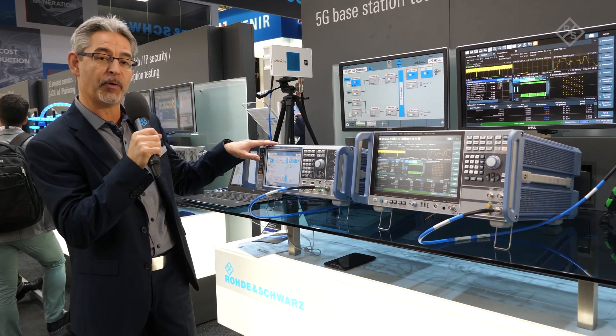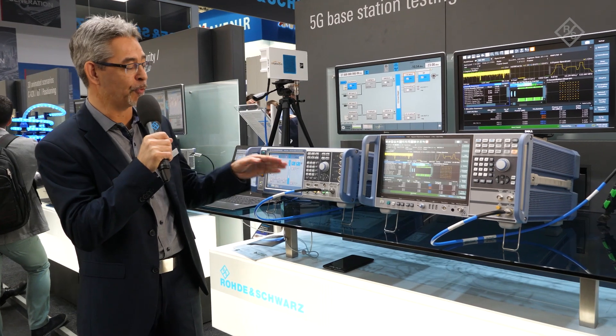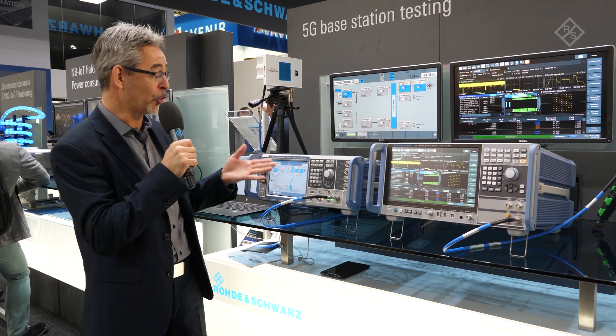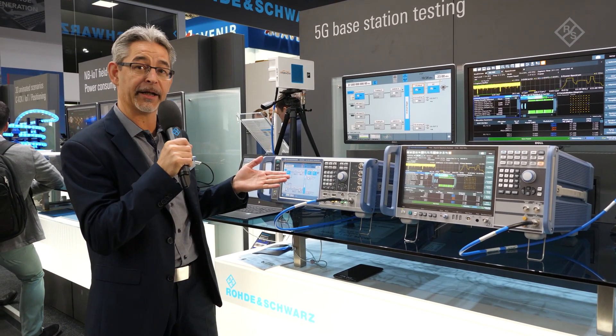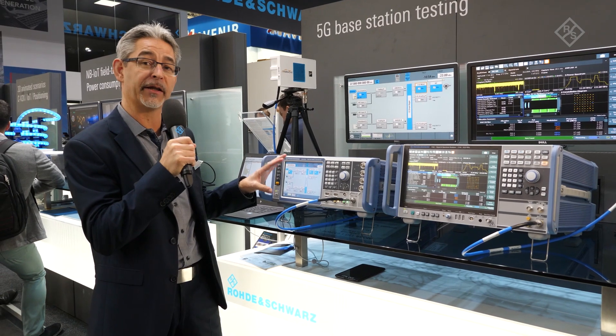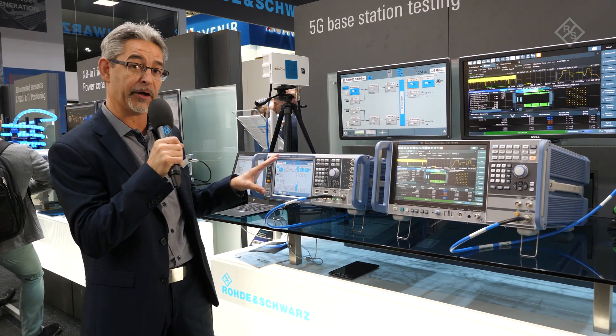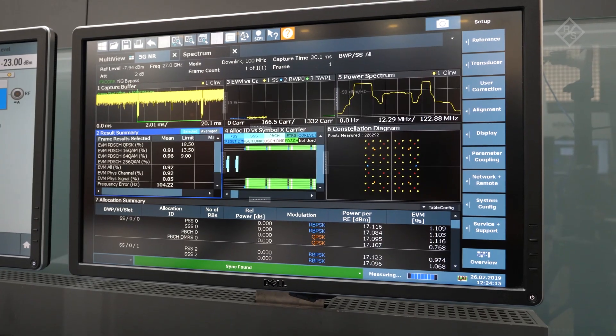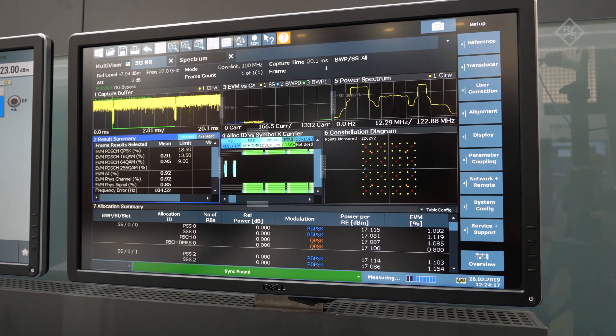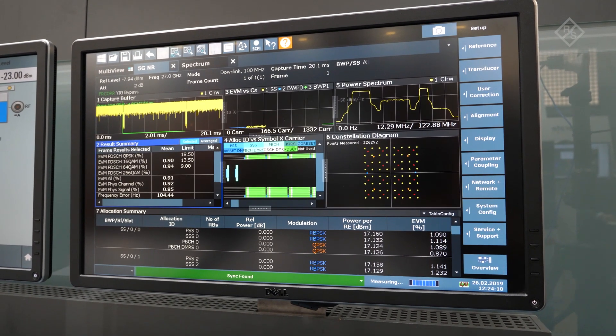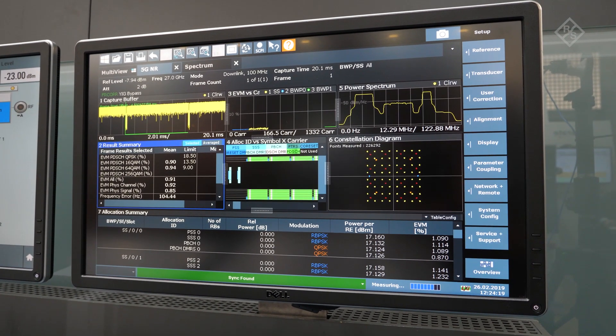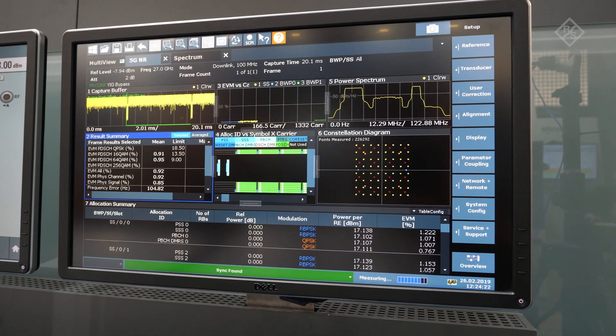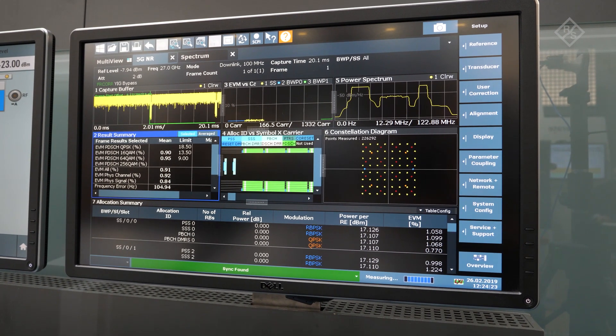We have extended the support for frequency up to 44 GHz on the generator side, and we also support fading now internally into the box with 200 MHz bandwidth. Both instruments are now capable of supporting FR1 and FR2 frequency bands, and they support the test models that have been specified by 3GPP.